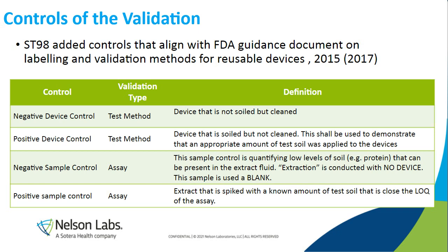There was a lot of discussion regarding what each control means, but we kept it the same as what the FDA thought process was, because it did make sense. I'm going to go through the controls, not in detail, but just give you an outline of what these controls will look like. There is a negative device control. Now, this is just a control that shows you that once your device has been processed through your chemicals for cleaning, there is nothing left on there that can introduce contaminants during the assay. So it is a control that shows that the detergents were removed through a rinsing process properly and did not interfere with any of the test results.